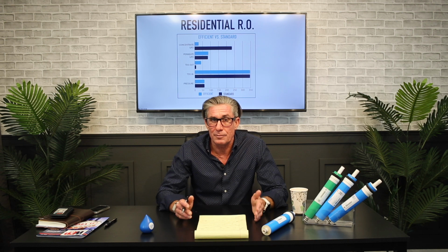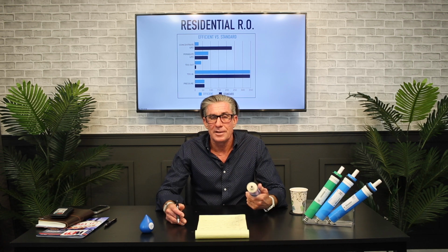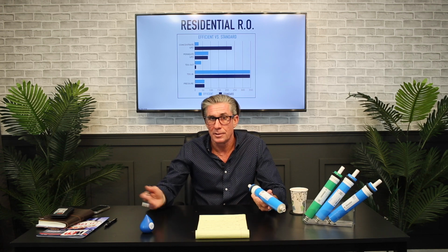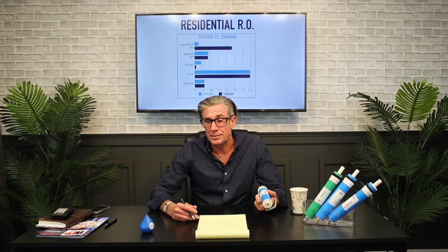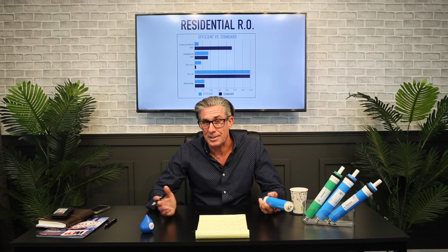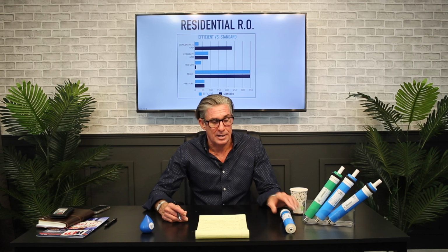So one thing, we're always going out and checking TDS to validate the quality of a membrane. Well, if your production has tapered dramatically, 50+%, you're extremely inefficient. So I would always recommend when you're testing membrane quality to look at the product flow rate. And if it's rated at 50 gallons a day, you can scale this test back pretty simply. Then it would be a gallon every 30 minutes. You can break that down into ounces or milliliters, whatever you're using, and judge it accordingly.